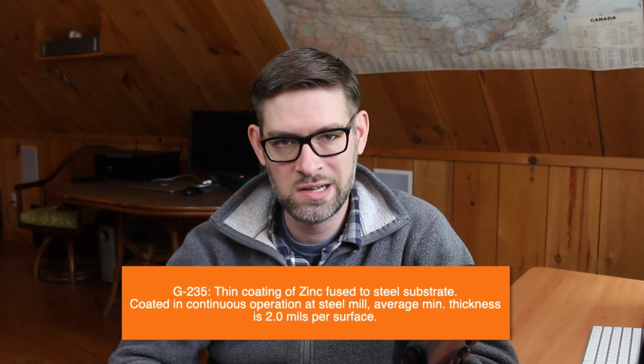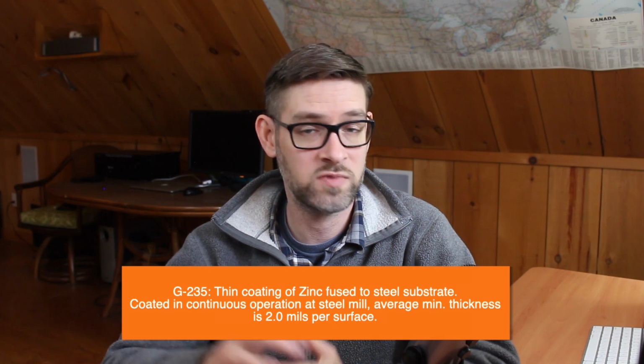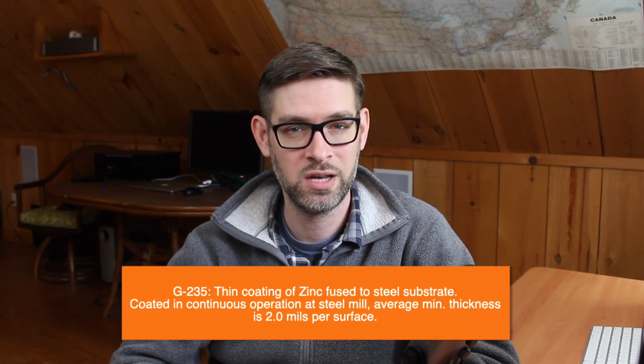Now, with that, the materials of construction of the basin are also very important. Commonly, galvanized G235 is applied as a standard basin material, but in areas of poor water quality, the 304 stainless steel can be applied. Now, the additional cost to go to a stainless steel like that is typically 10 to 15% on the total cost of the tower, but the added life that you get from that basin is tremendously extended. So it's a great option to add.